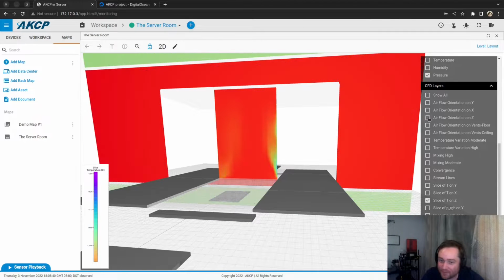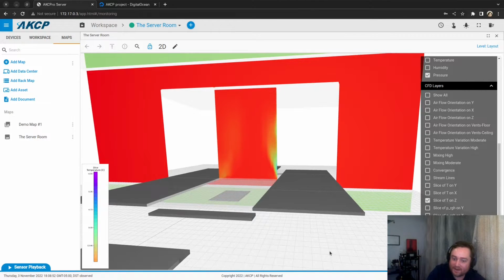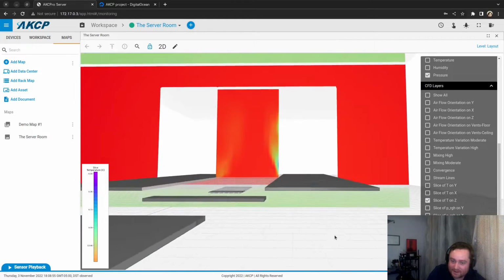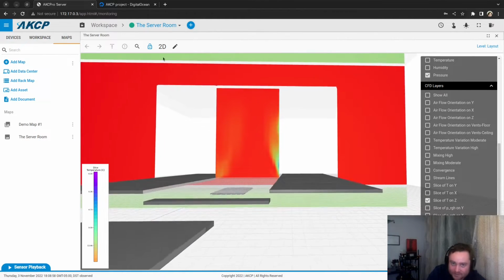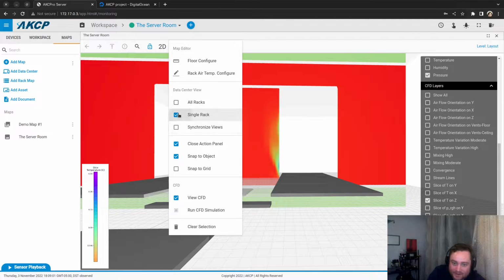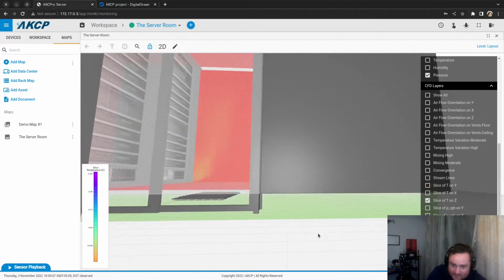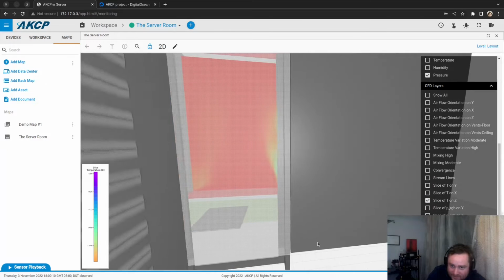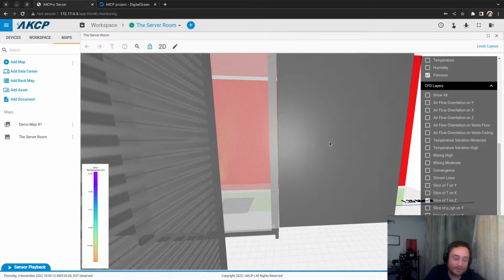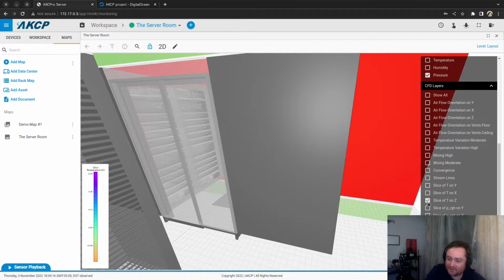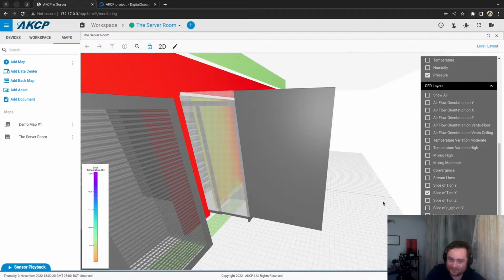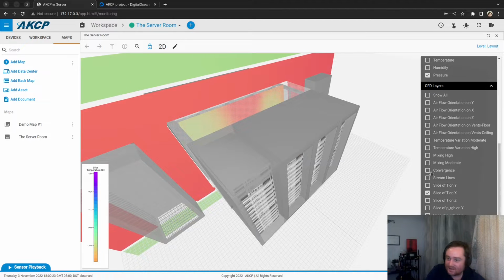So if you remember, when I usually click on the size of the temperature, we got blue and red, and everything is really well split, but not in that case. We already see that we got some air that gets under the rack. So when I go in the mode like that, the racks are on the floor. So just put all the racks, yes, like that. So the air goes under, and I think not cool down, heats the inside of our containment.